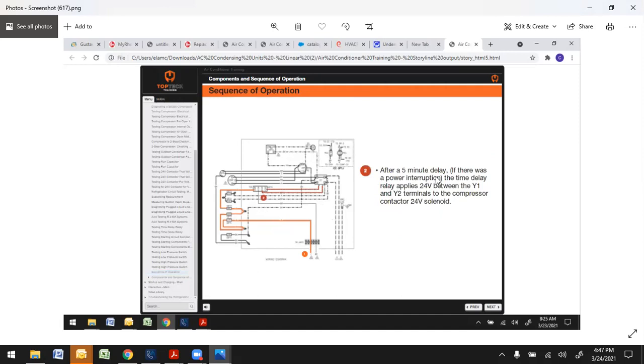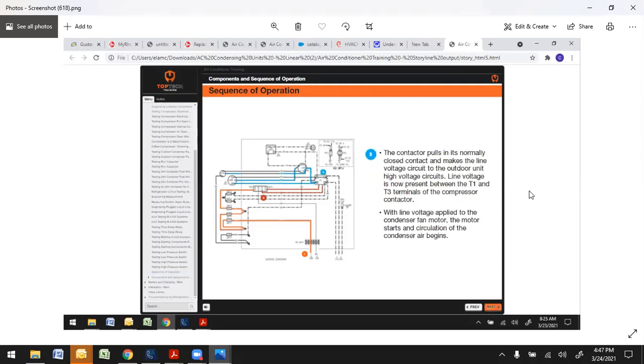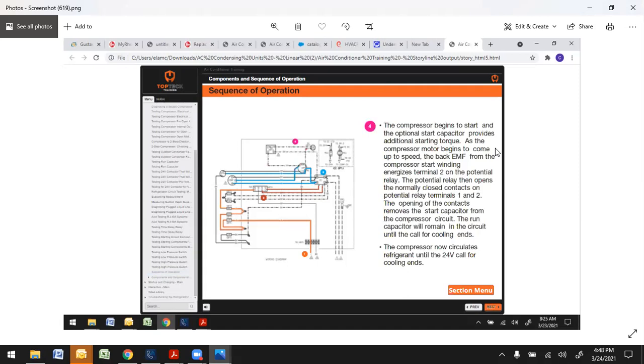So after your delay, if it's in the system, at that point, 24 volts hits the contactor, and your solenoid is engaged. Once your solenoid is engaged, the fan motor and the compressor should turn on simultaneously. Once the line voltage is applied to the fan motor and compressor, circulation of the condenser air begins. The compressor begins to start, and the optional start capacitor, if that's in there, provides additional starting torque. That just makes the compressor start a whole lot easier.